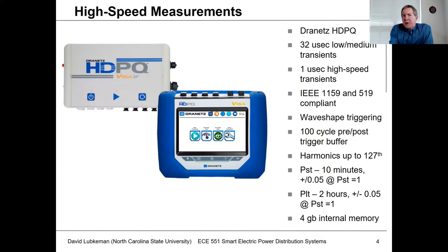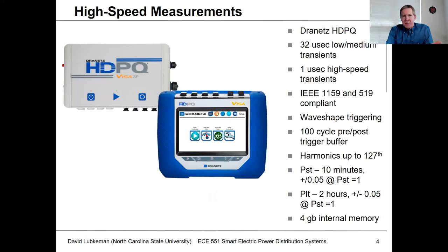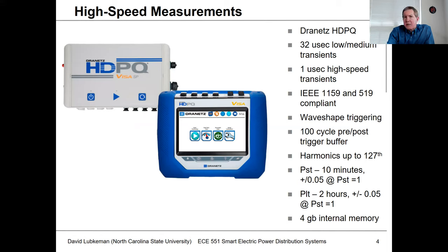Your experience with measurements at this point may have been using a handheld meter or an oscilloscope. With a handheld meter, you're taking measurements in roughly the second timeframe. Utility SCADA systems monitoring top-of-feeder voltages and currents or pulling off recloser values are typically in a two-second time interval. But if you really want to see what's going on sub-second, you typically need higher-end measurement systems.